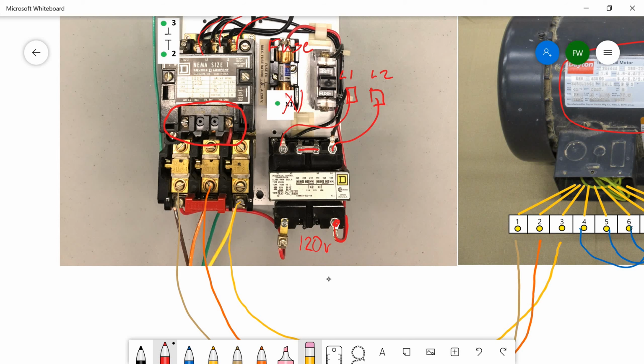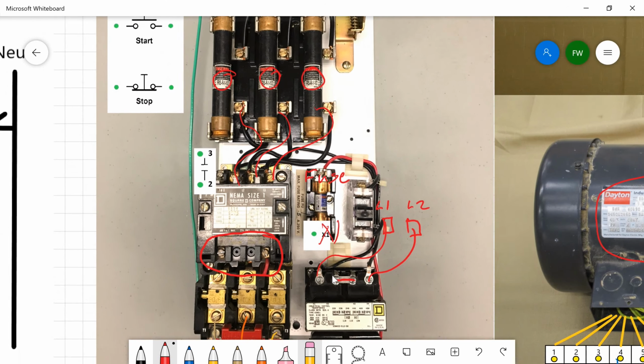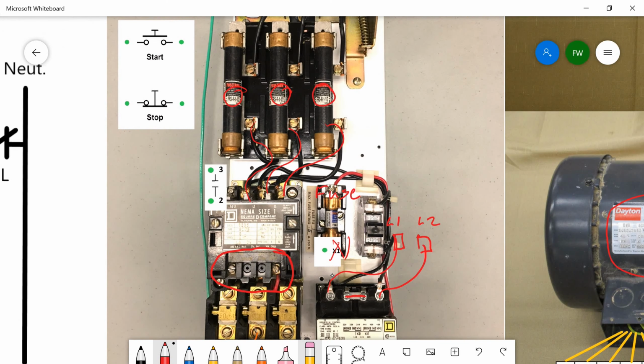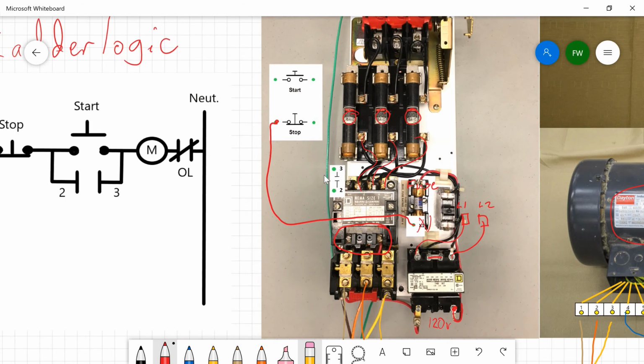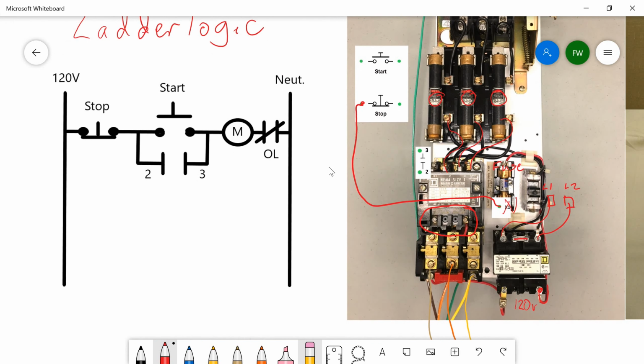So let's start with the hot side first. One of the very first things is we need to get a hot to our stop. So let's drag X1 and we're going to take it to the stop terminal of our start-stop station. If we were doing a more complicated diagram, we'd be checking this off. In this one, it's pretty straightforward. So we've got 120 volts coming in, so we're going to connect to our stop. Now the next point that we need to hit is we need to go from our stop to our start. So we do a little jumper from stop to start. That'll complete the next leg.